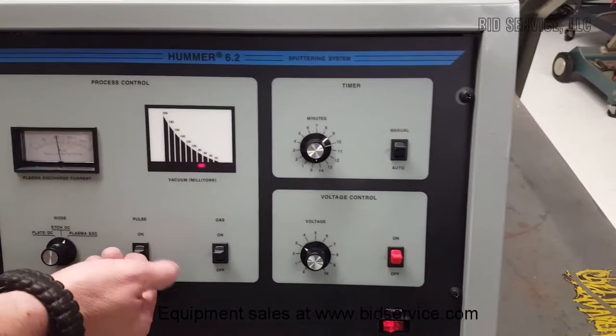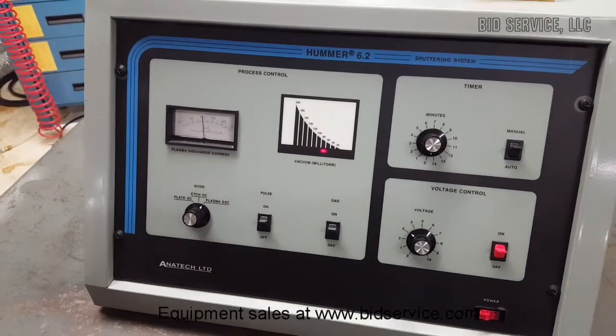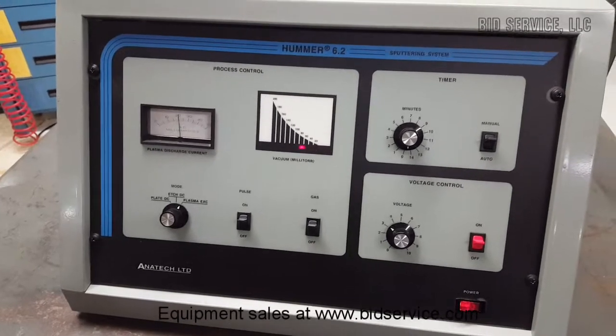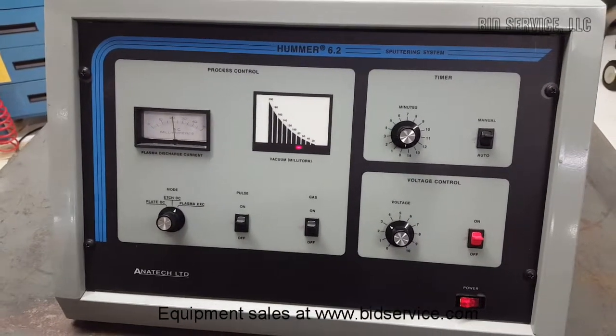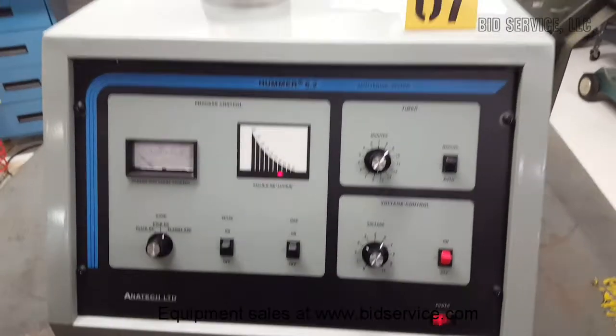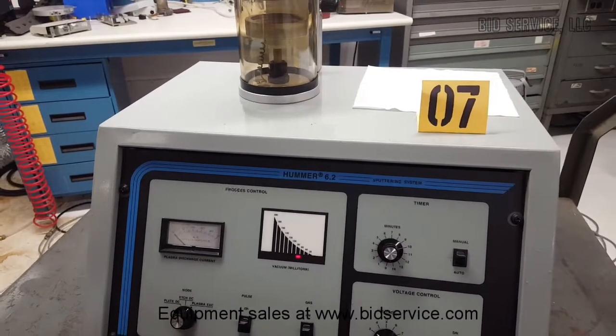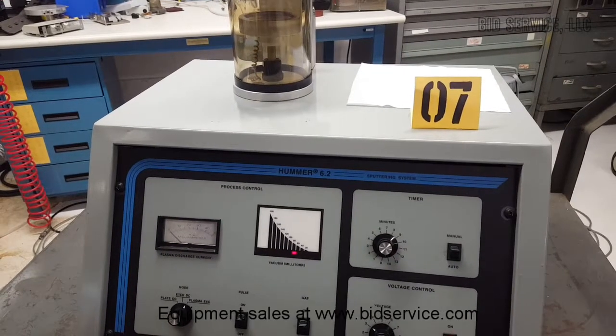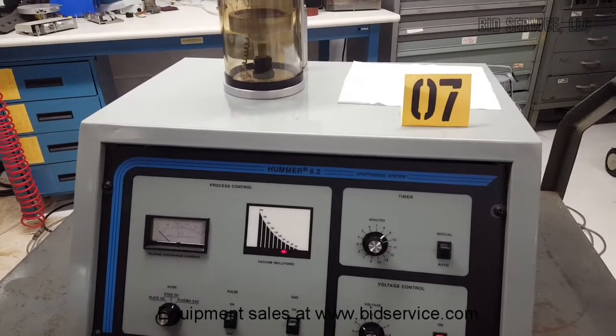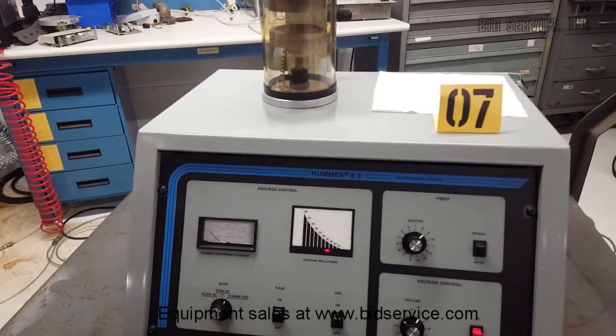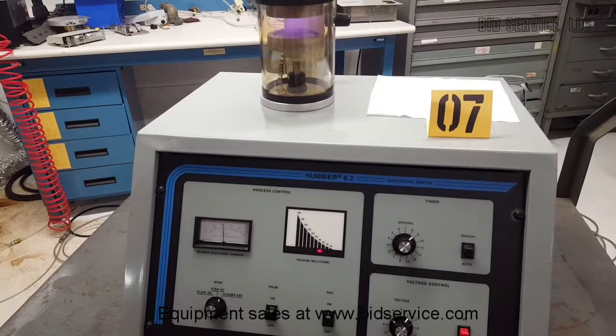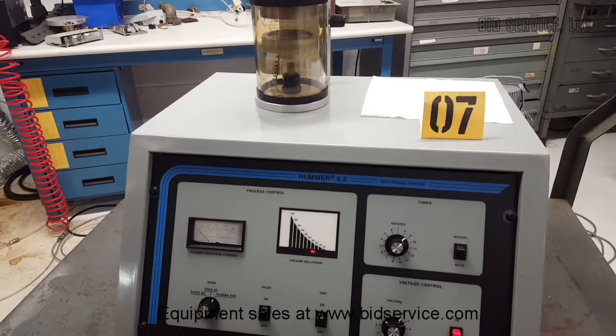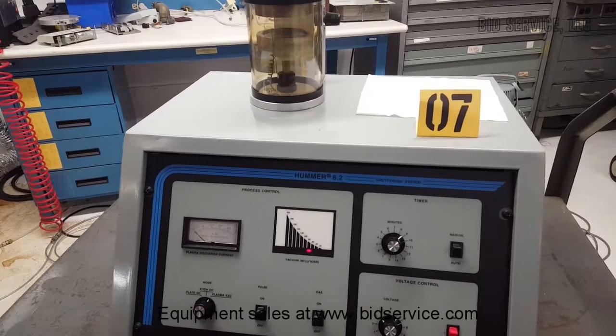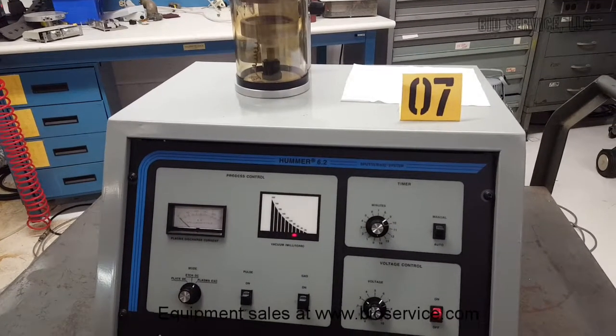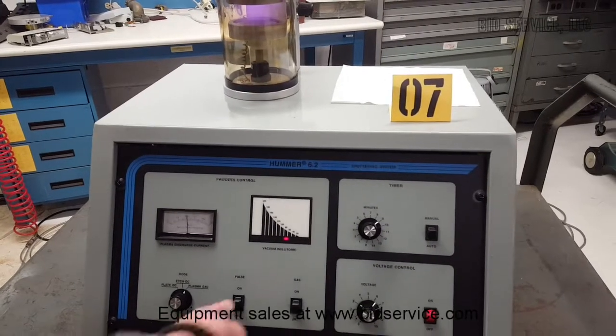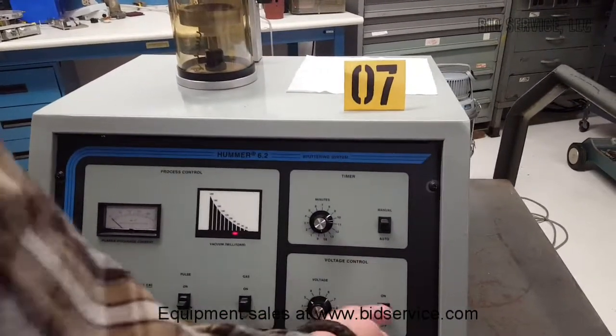And pulse mode can be used in any of the 3 modes, and basically it's just an on-off mode, so that it reduces potential heat on your sample. So now it'll be off for a certain amount of time. And it's back on for a certain amount of time. The first off cycle is the longest. So besides pulse mode then, let's turn this down.